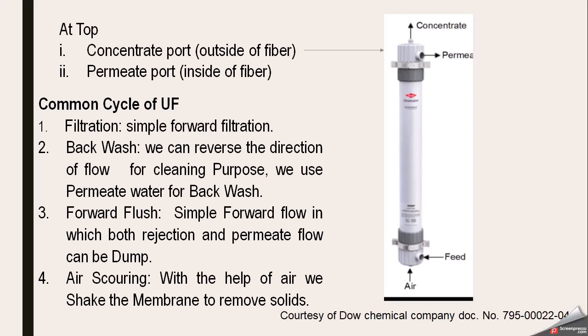There are different operation cycles in UF. The first is filtration — simple forward filtration in which water goes from outside of the membrane and, with the help of pressure, comes inside the membrane. This is outside-in flow, with a dead end at the top. Water enters from the feed on the outside and comes out from the inside as permeate.